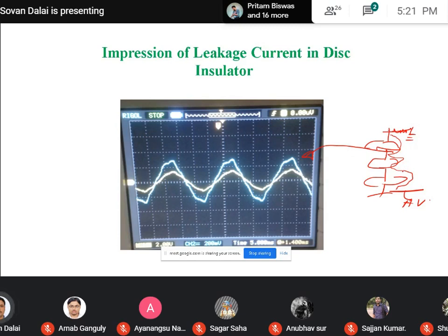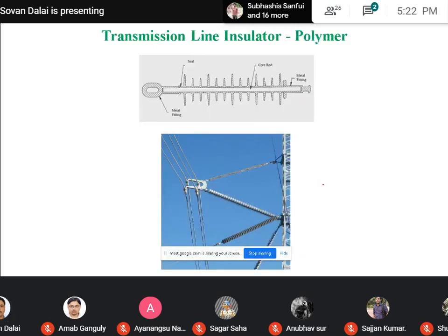There are two types of breakdown related to the insulator. One is called flashover, another is called puncture. Flashover is basically the breakdown of the surrounding air over the surface of the insulator, and puncture occurs through the insulator, and this is the permanent damage of the insulator. So that is why people are interested to monitor the leakage current over the surface of the insulator.